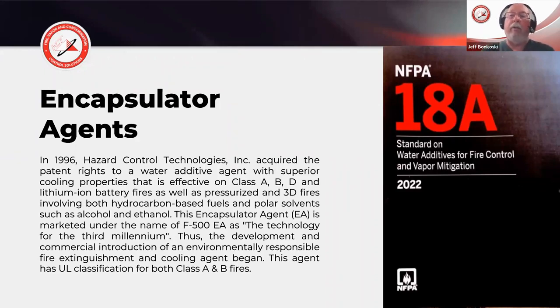There's a standard for it: NFPA 18A, the standard on water additives for fire control and vapor mitigation. I mention that because throughout this presentation we've talked about reducing toxic vapors and toxicity from the batteries. Water doesn't do it. The inerting gases don't do it. The foams don't do it. The powders don't do it.